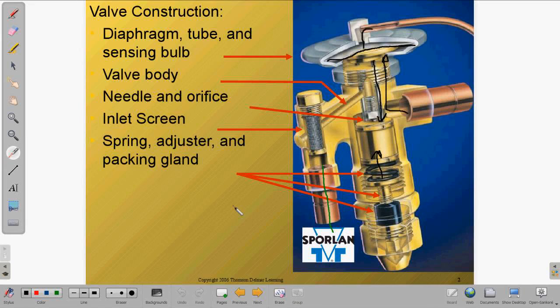If we have a TXV valve that isn't operating properly, and what can go wrong, there are times, and I've seen it happen, it's an expensive repair for the customer, but due to improper installation practices and brazing practices, debris gets caught up in the screen right here, and it will plug off. It'll start to plug up the refrigerant flow and hold back this refrigerant flow, and it's going to start to starve the evaporator for refrigerant. There's absolutely no way to check that unless you pull that out and check it and clean it and put it back in again.